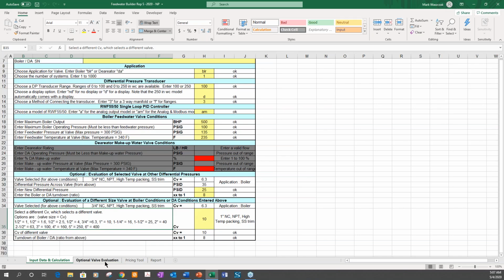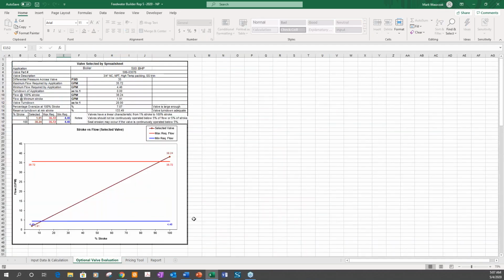Next, we go to the tab at the bottom, which says optional valve evaluation. And what it will do is provide you with three charts. The first chart is based on the conditions we put in and how it selected a 3/4 inch valve. And you'll see that the min/max flow for that valve is 1.91 gallons per minute up to 38.24, and it falls within the range for this application.